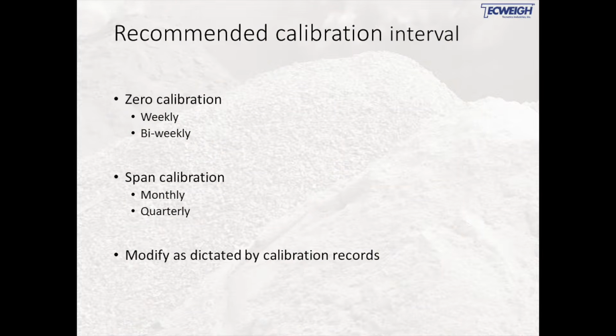People often wonder how often you should calibrate a belt scale. It's a good idea to zero once a week at least. Zero daily is even better. You can put the weights on and do a span calibration once a month, maybe once a week, or even once a quarter. You should really modify that or make your calibration around how often your belt scale is shifting. And remember, the belt scale is not really shifting. The dynamic forces on the conveyor are what's changing. So the idea about good installation and good routine calibration is reducing the effects of those dynamic forces.